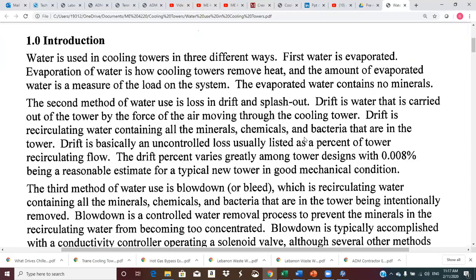That's water that is recirculating through this cooling loop, and it contains minerals, chemicals, bacteria, all the crud that's in the recirculating water, and that gets carried off because it's not evaporated. These are droplets that get carried away. It's pretty much an uncontrolled loss, listed as a percent of tower recirculating flow. We do have drift eliminators, they're called eliminators, but they don't totally eliminate it, but they will reduce it.